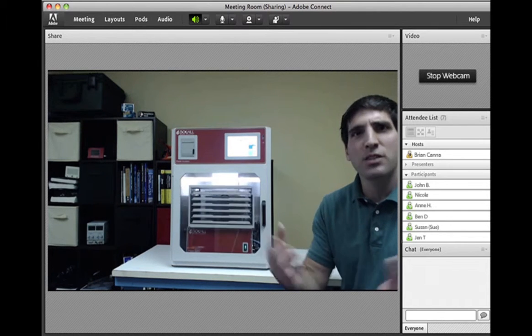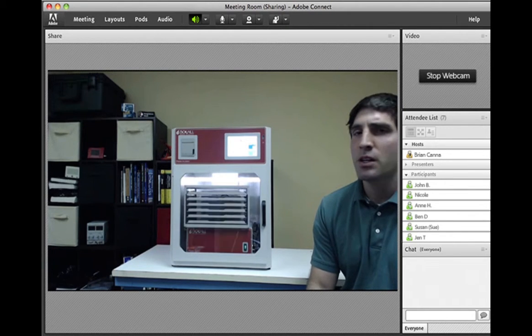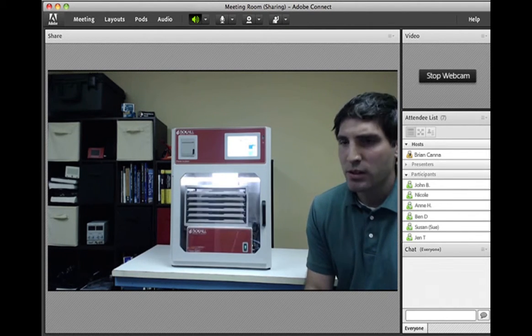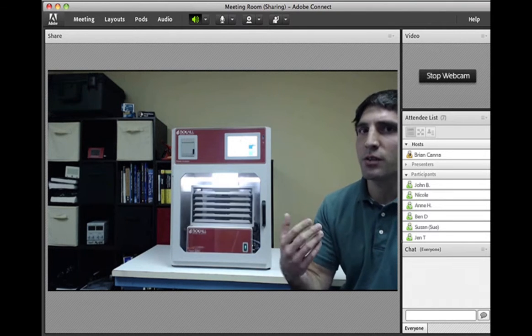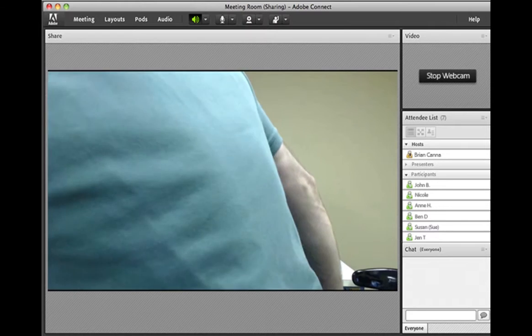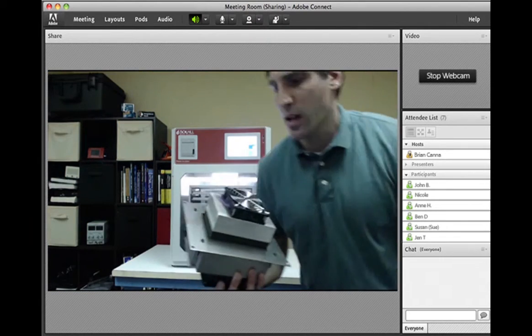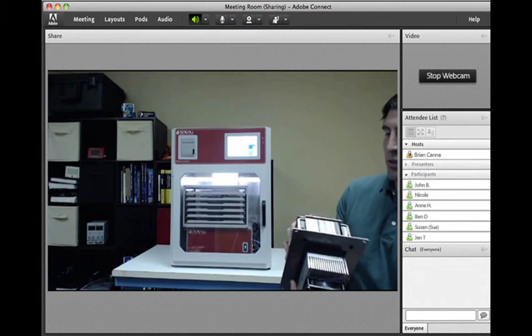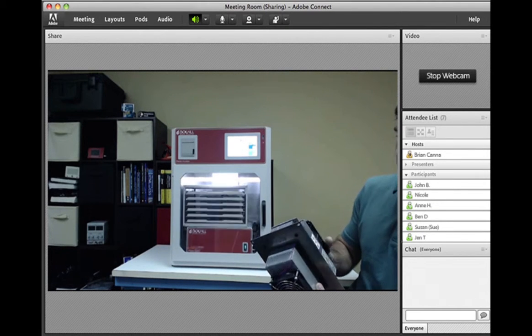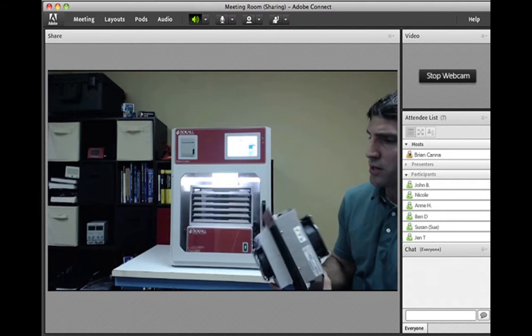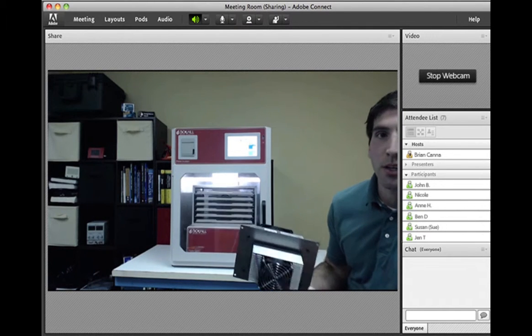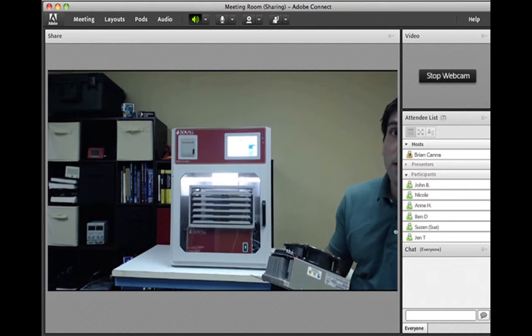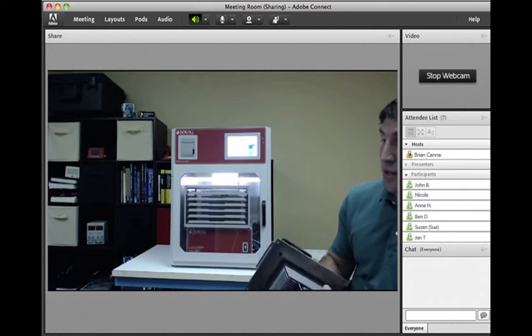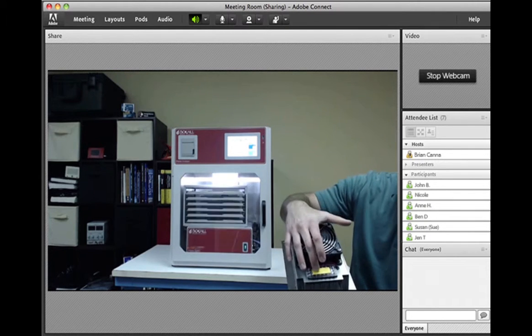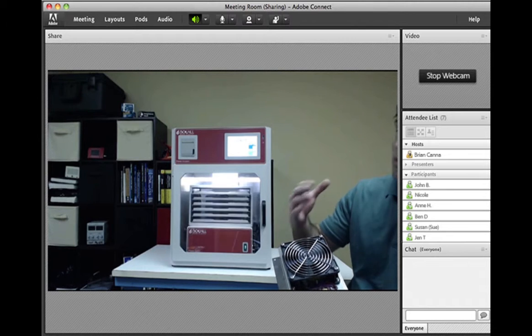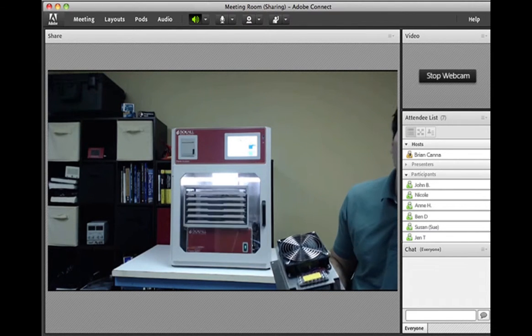So it's more of a digital type control. It's either on or off. You can't run a compressor type system at 50% because it just won't work. It has to run at 100% or off, and I actually have one of the Peltier units right here. So this is it. I'm not sure what size this is, but this takes the place of all that refrigerant and tubing and a heater. Yeah, there's no resistive heater inside the system to then add heat to the system. This does it all. Electricity is passed through here, and depending on whether it needs to cool or needs to heat, that's which way the electrons will flow.